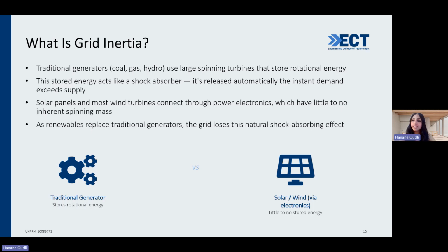If a larger generator suddenly trips, generation is no longer equal to demand, so system frequency begins to fall. Rotating machines don't need a control signal before they respond, because of that high inertia, that physical shock absorber, that mechanical buffer. Their stored kinetic energy is already physically coupled to the grid, so energy is exchanged immediately as the rotor slows. That gives the system time, which is important.